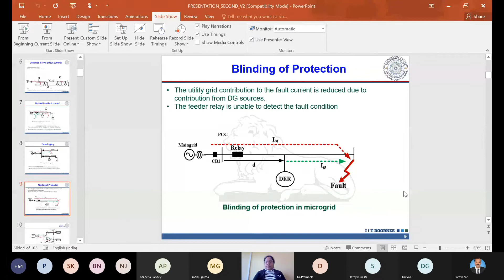So this is the fourth issue, the blinding of protection. This is another major issue which has been handled by many researchers, and they have published many papers. It is even going to be included in the patents of many companies. This blinding issue is a major issue. What is that? Suppose you have this main grid system and this one feeder, and here one fault is created at this point. Due to this fault, this main grid will supply some current and this DER will also supply some current. So together the two are going to contribute to the fault.